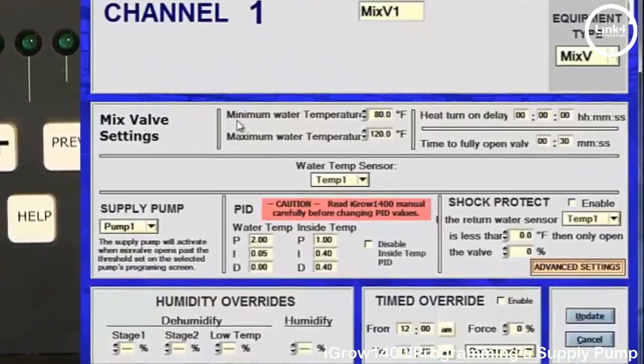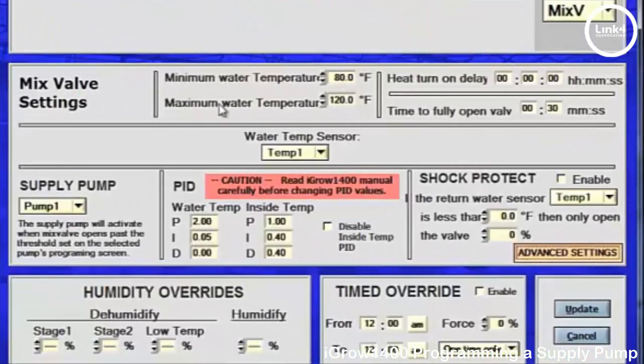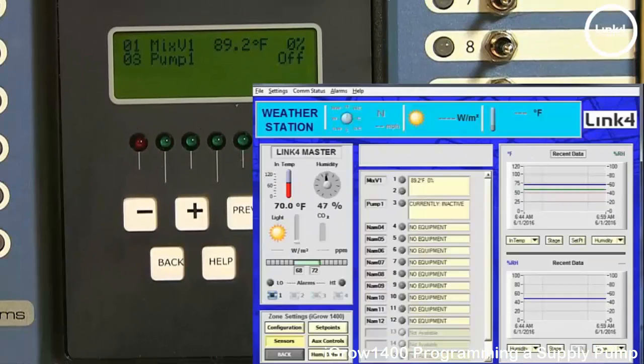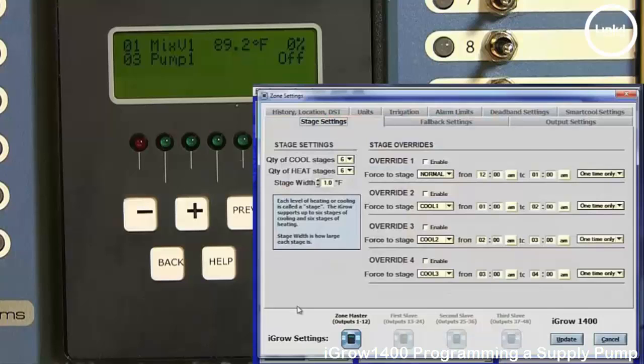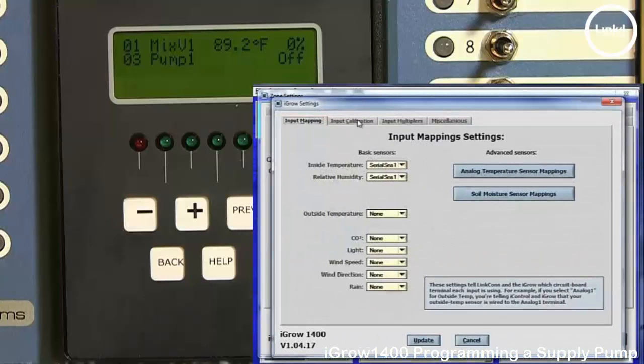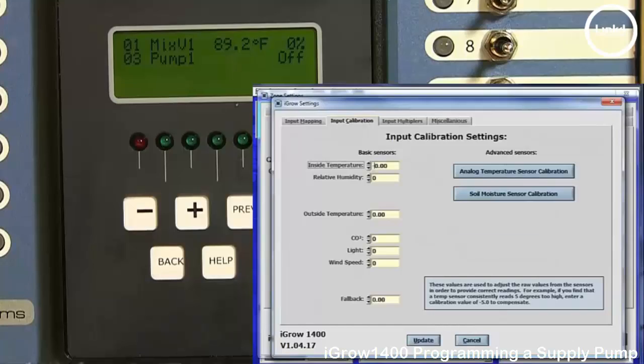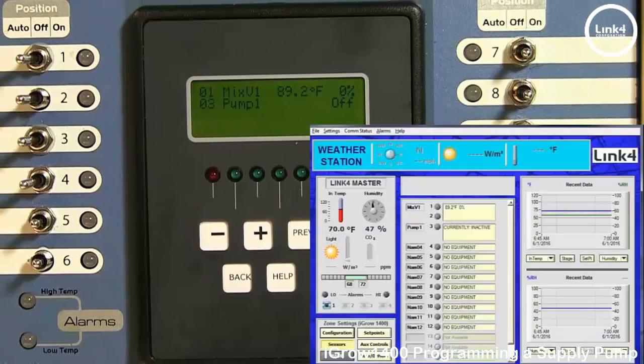Now with the mix valve settings, it says minimum water temperature 80, max water temperature 120. Now if the temperature falls below this 80, this mix valve will in fact open, and if it opens beyond 5%, the pump that's supplying this mix valve will in fact turn on. So what we're going to do is just simply manipulate the temperature sensor associated with this mix valve output, and we're going to change the calibration to be minus 10 degrees.